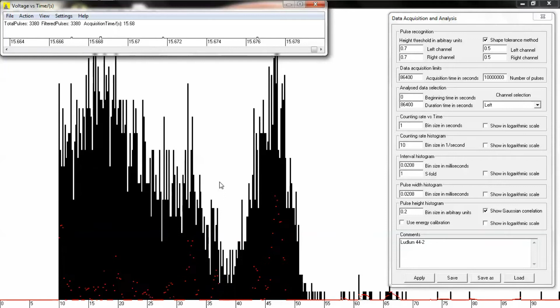So the first thing we're going to do is go to Action, and go to Start Pulse Shape Acquisition. Now this may look like a spectrum forming, and sort of in a way it is, but it's not really, so just don't worry about it. I'm going to collect a few thousand pulses, and what the computer is doing is figuring out approximately what is a peak versus what is not a peak.